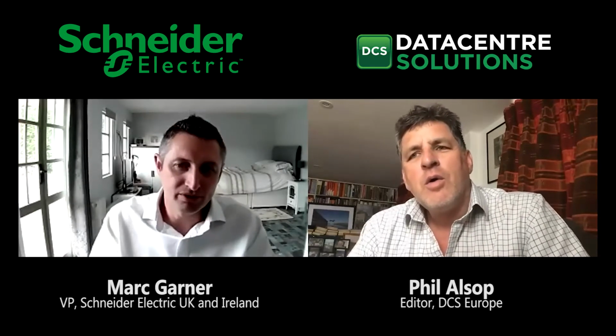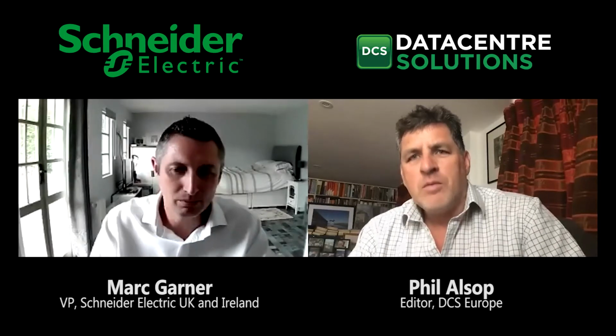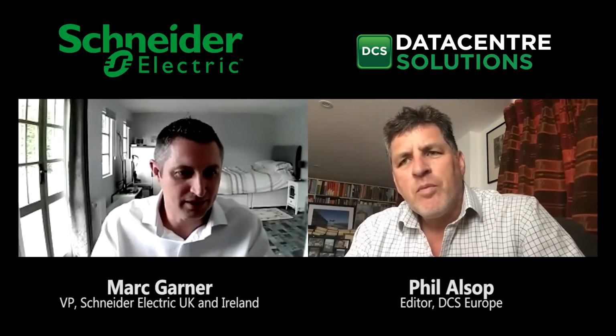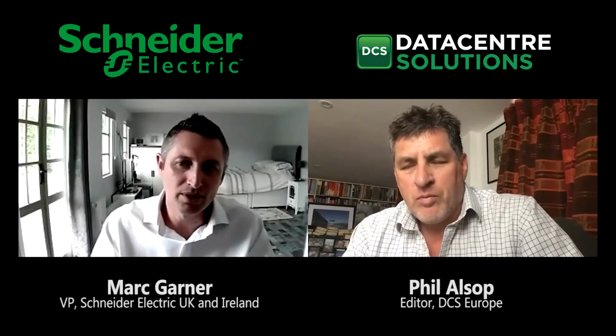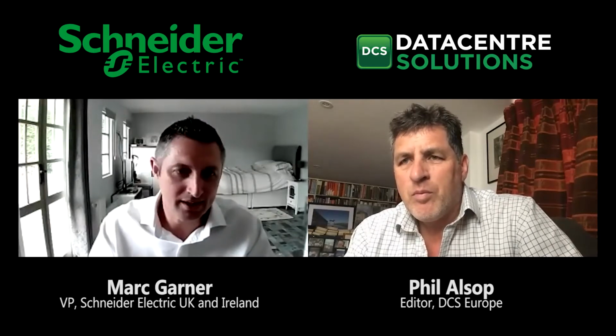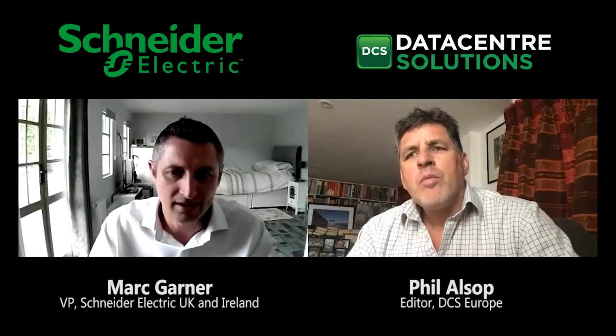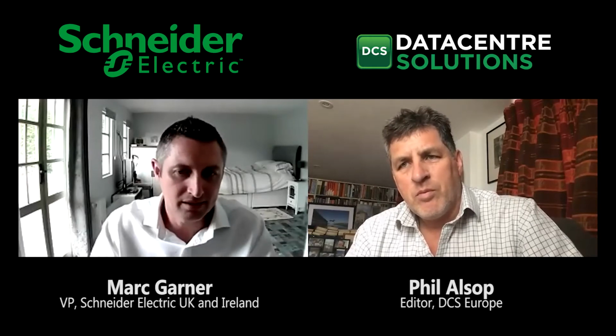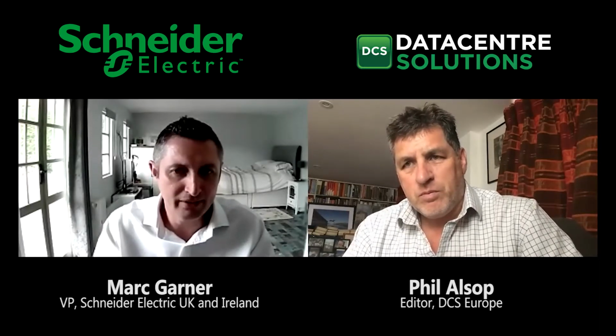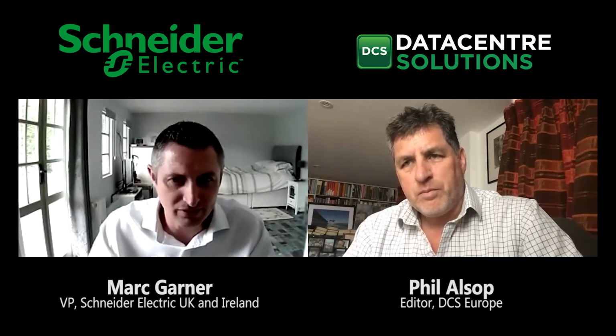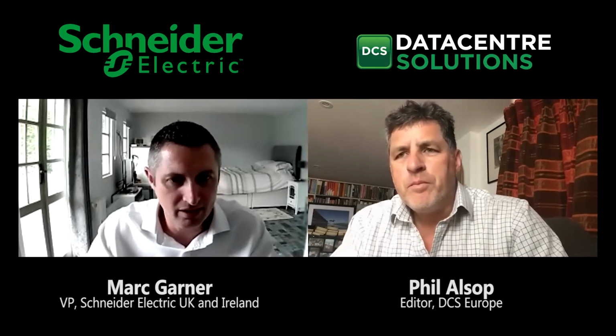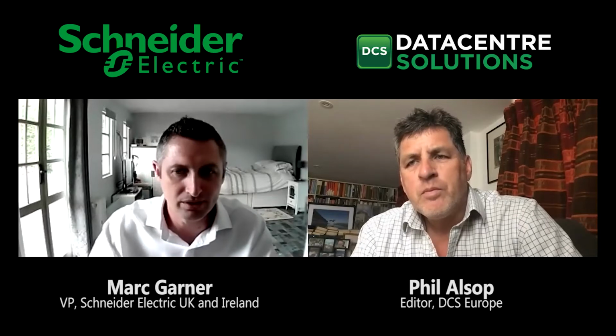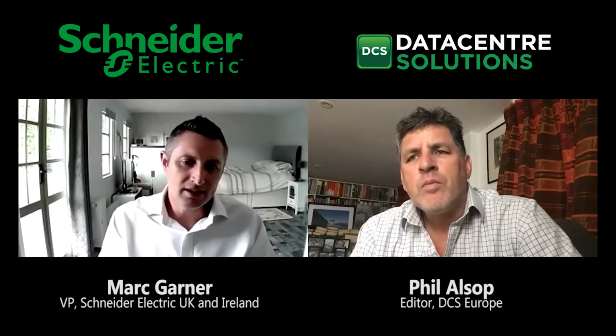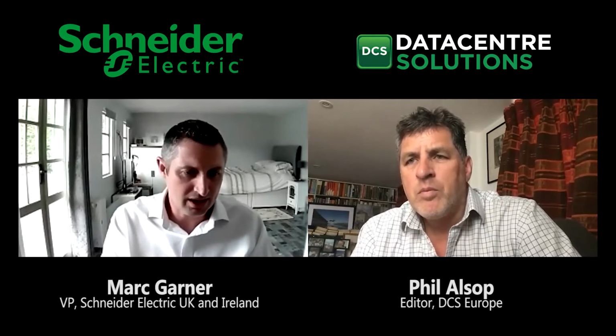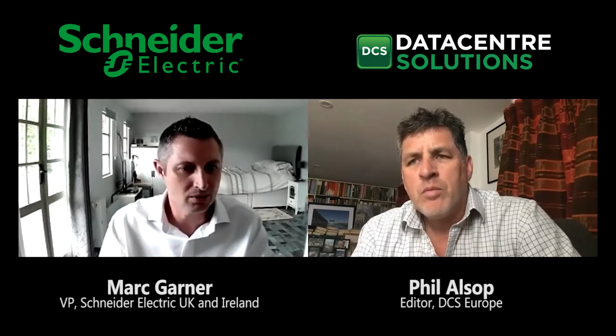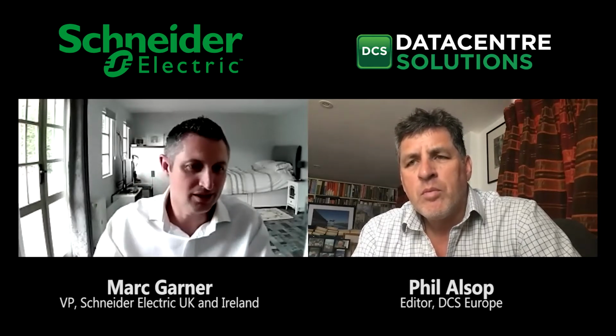Where possible, for us to hit the lead time - one of the main feedbacks we've had from customers is around speed of delivery, how can we speed up that whole process. For us to do that, the option is to standardize as much as possible within the Easy Modular Data Center. So we've got 4 standard form factors, ranging from 5 to 14 racks, offering power density between 27 kilowatts and 94 kilowatts. They come pre-configured in either an ISO 20-foot container or an ISO 40-foot container, and the design is standardized around Schneider Electric's Easy range and Easy solutions - so we have our Easy racks, Easy PDUs and Easy UPS going in there.